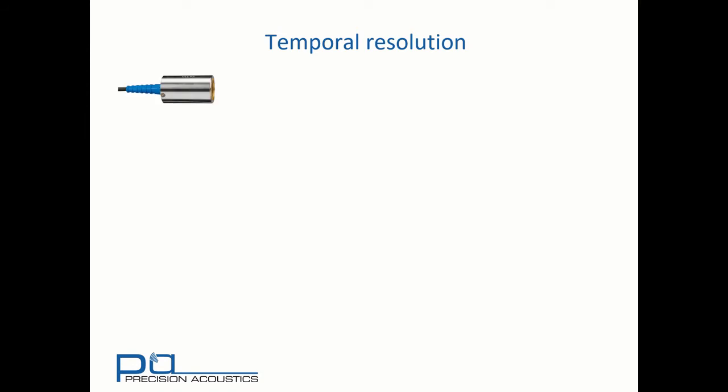Consider here a transducer that's being used to interrogate a sample. We'll be looking at this sample pulse echo. So as the signal radiates from the transducer, some of that signal will reflect from the front surface of the sample and will be shown on the time trace.